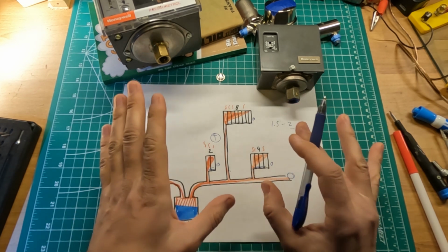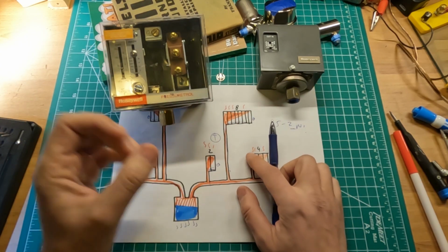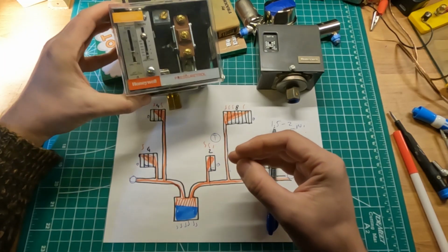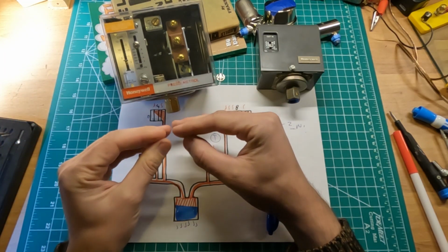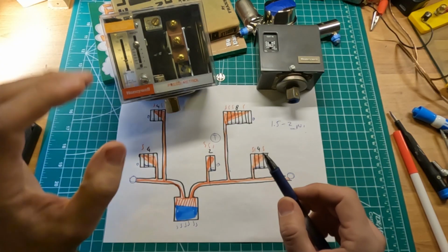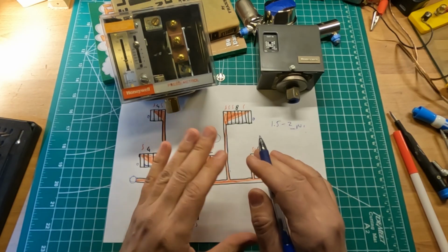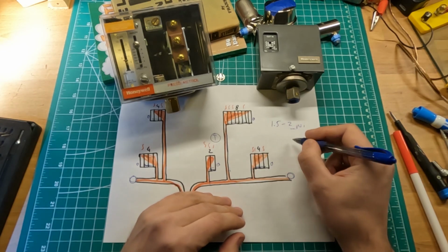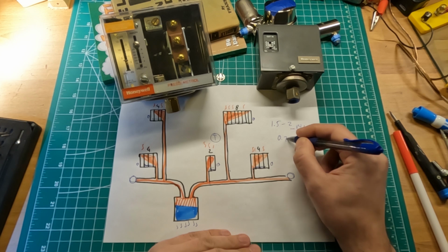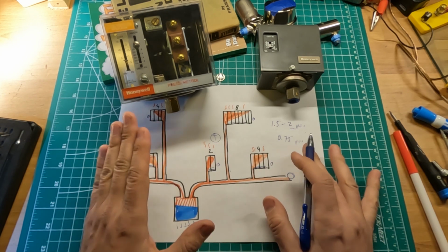If you have access to more precise control devices, that is not Pressuretrols but this thing called a Vaporstat. A Vaporstat is basically like this Pressuretrol, but the diaphragm right here is much bigger. Because of that, the manufacturer can deal with a bigger or more nuanced pressure increase, and you can set the Vaporstat to very precise settings. So if you have a Vaporstat, and neither of those are Vaporstats, you can set your Vaporstat to shut down the boiler at say 0.75 psi or something. Again, we don't want pressure inside your system.